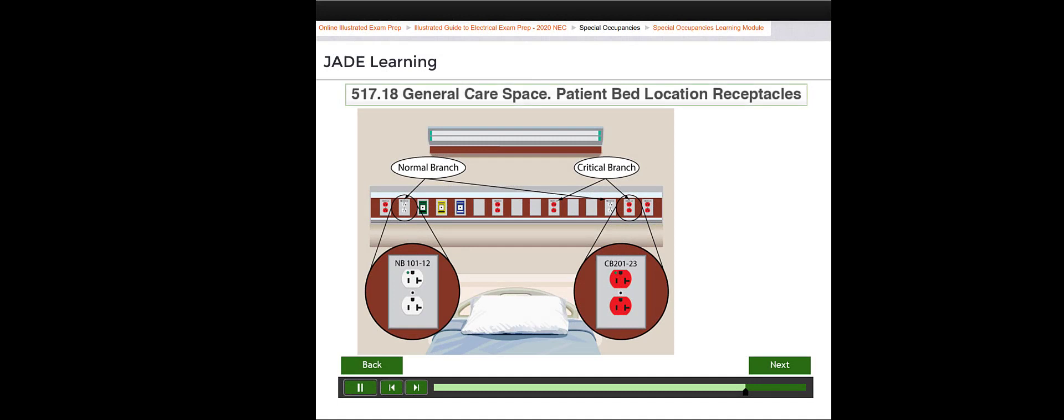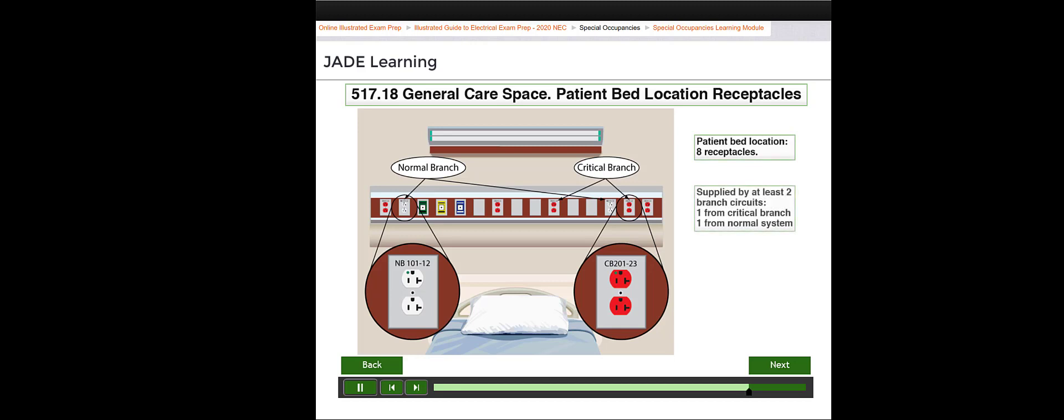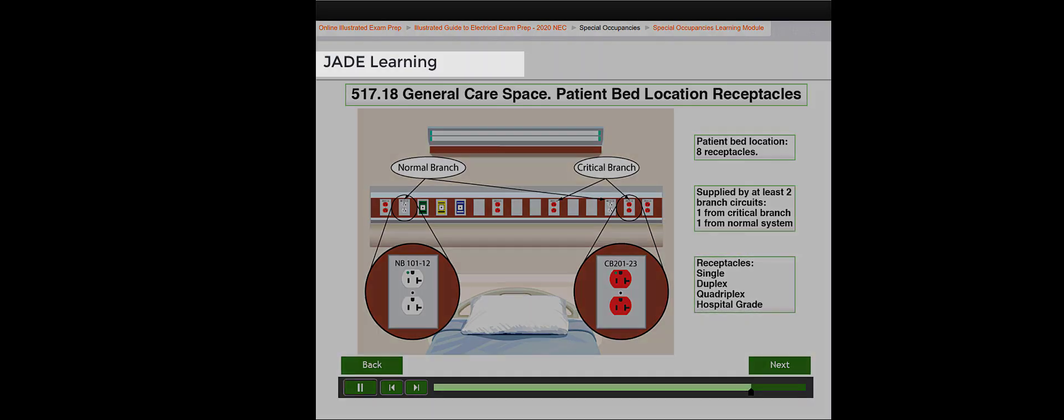A patient bed location in a general care space must be provided with a minimum of eight receptacles supplied from a minimum of two branch circuits. The receptacles may be single, duplex, or quadruplex.